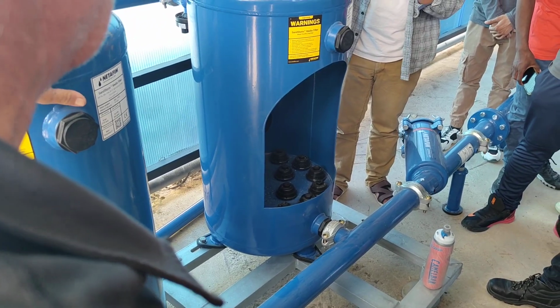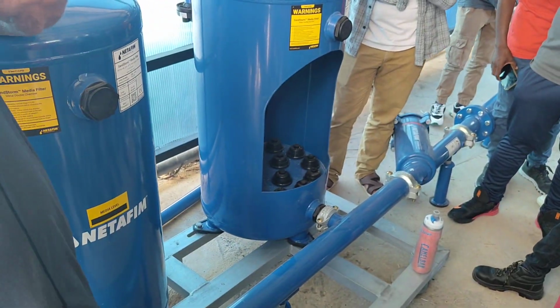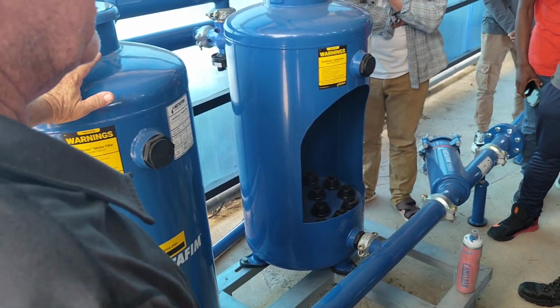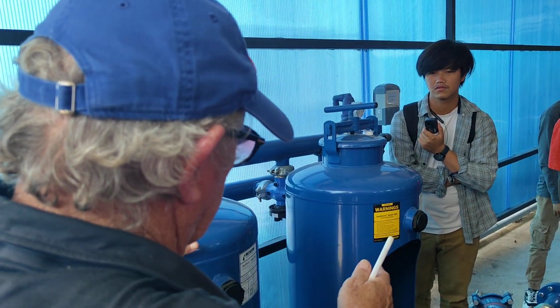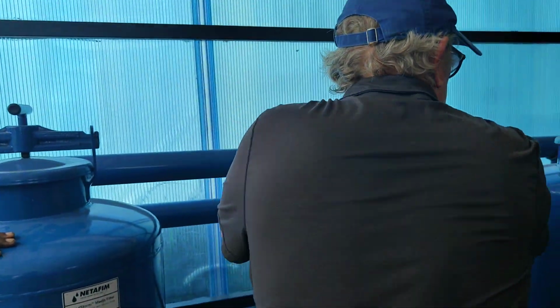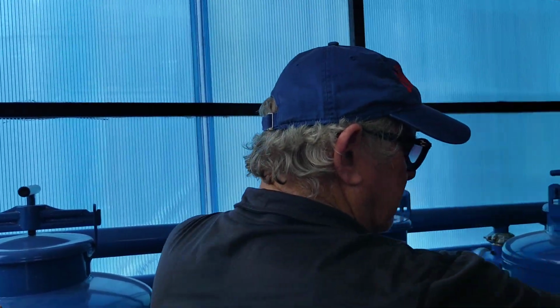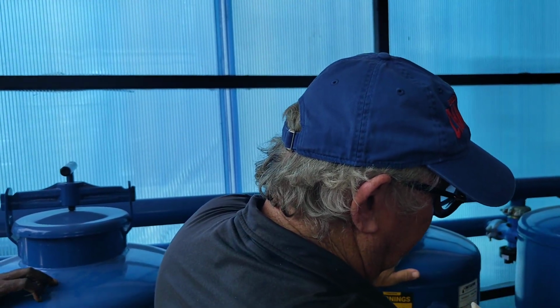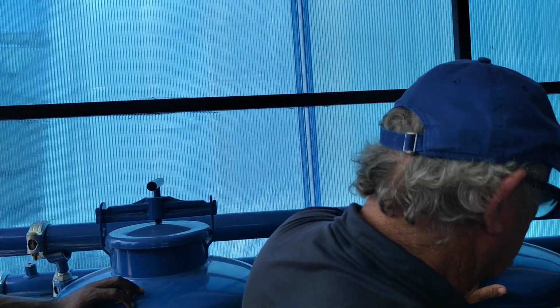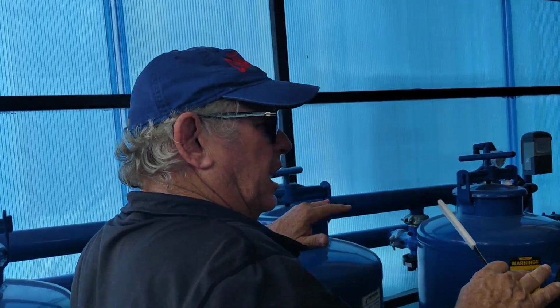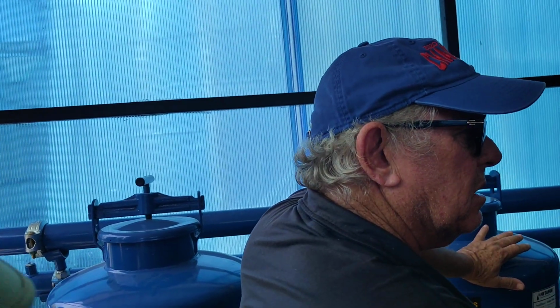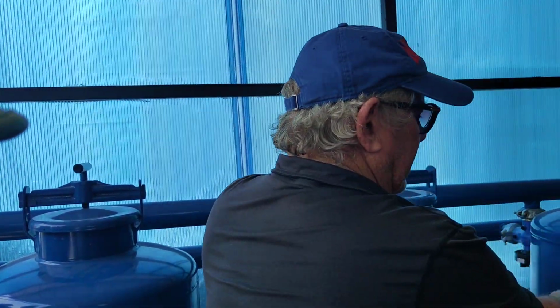And the functionality is that those valves located here have a double purpose. Once they permit a situation of filtration, which means that the valve is open, the water goes down and straight to the field. When the time comes, the media, which is usually sand or gravel, is blocked because of the dirt. This valve, located here, changes position. It goes down instead of up. The same valve, by hydraulic order, and the water which comes from these two filters, which is filtered water, very clean water because it has already passed the filtration, comes and goes up and cleans the media.